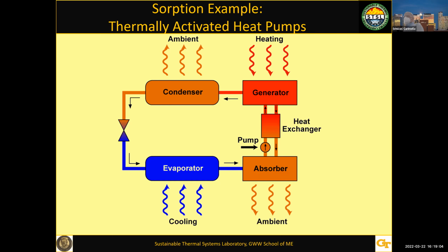One approach is to take heat, which could be solar energy, biomass, or waste heat, and use it to boil off a refrigerant at high pressure. The rest of the cycle stays the same: condenser, expander, evaporator, and then you absorb it back into the liquid in the absorber. Now you're pumping a liquid instead of compressing a vapor, which requires much less electricity.